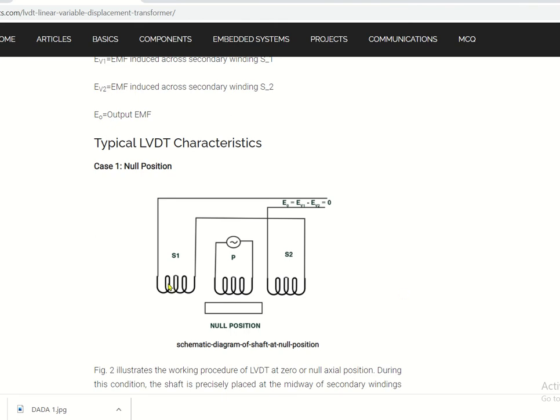Now let us see in this diagram, it has been very clearly depicted that we apply the signal across this primary and we measure the voltage that is developed across these two secondaries. Here you can see this rectangular portion. This actually signifies the dynamic core. So this core can move. Please do not keep the idea in your mind that we are using an air core device. In between the windings there is a movable core. And since this core is movable, its position ultimately decides how much magnetic flux will be linked between the primary and the secondaries.